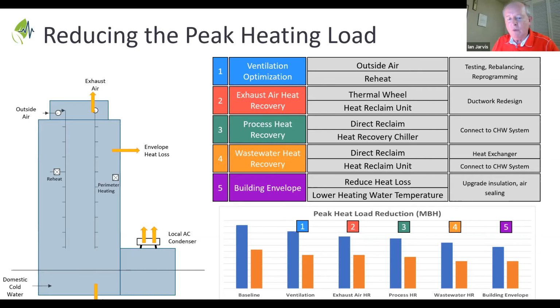We cannot see at the moment how in the short term we're going to get free of boiler plants altogether. We are looking at that with commercial office buildings, for example, but hospitals are going to have boiler plants for some time to come. The key is to make those new plants as small as possible by implementing elements of peak heating load reduction, so that when we do replace our boiler plant, it's right-sized to the future energy efficient load profile, which leads to lower cost installations and to more efficient plant operation.